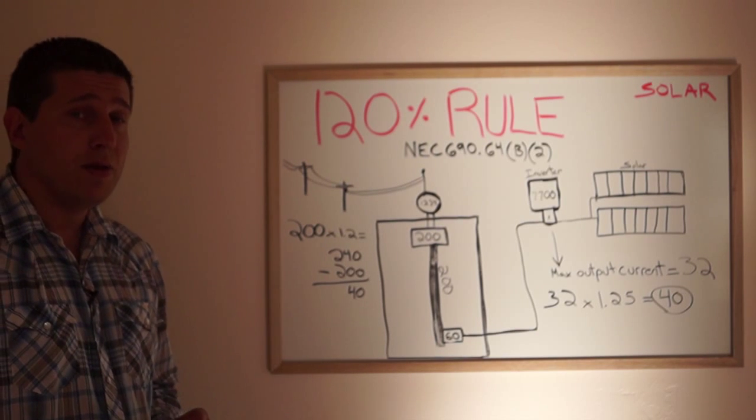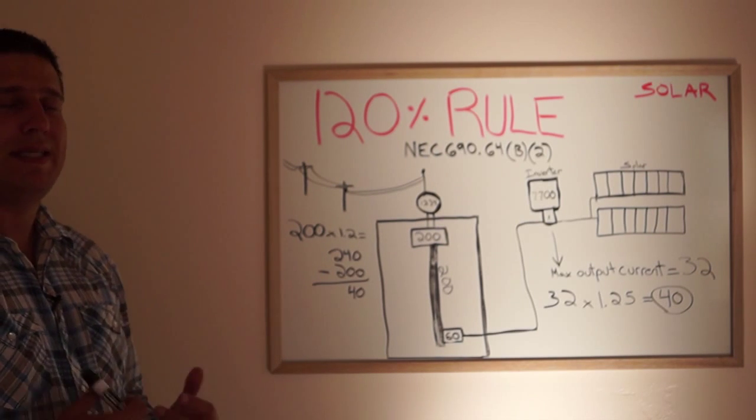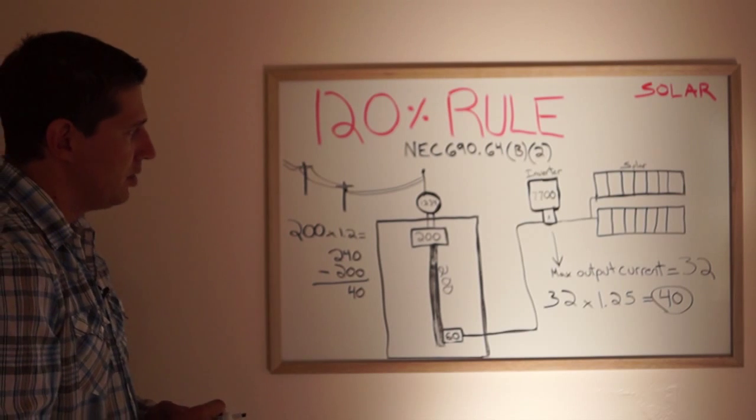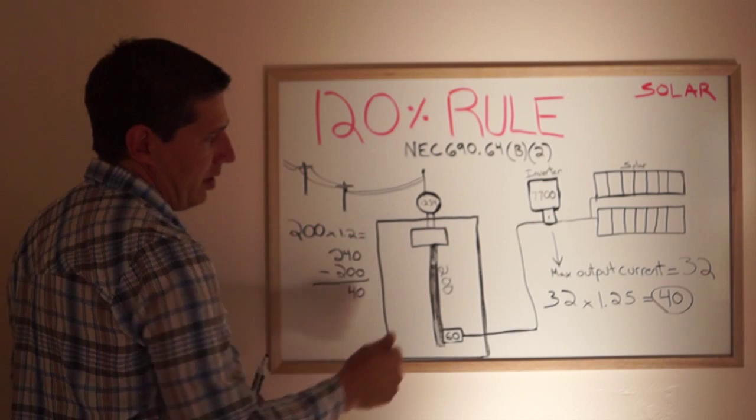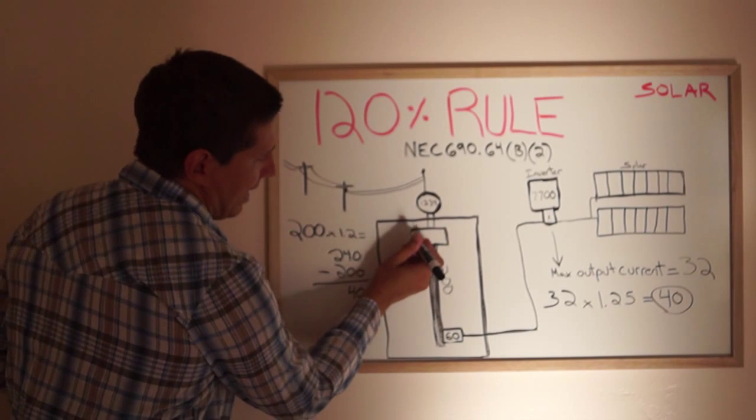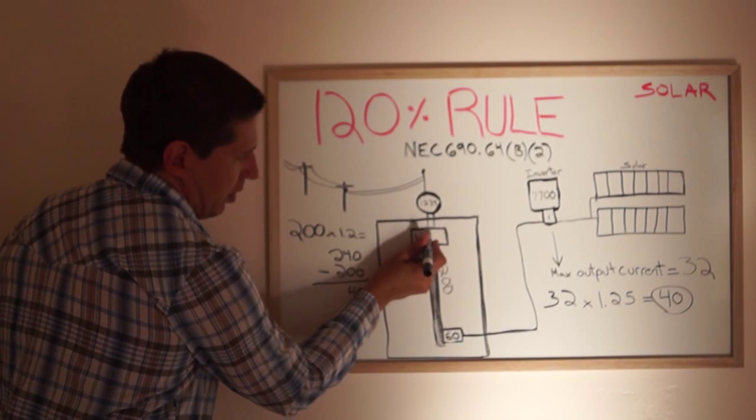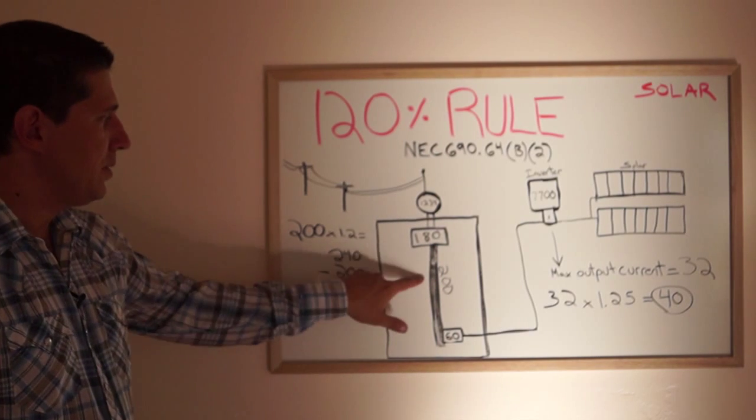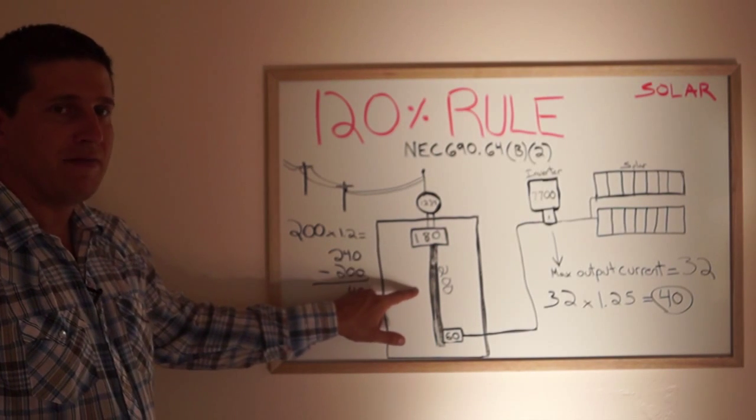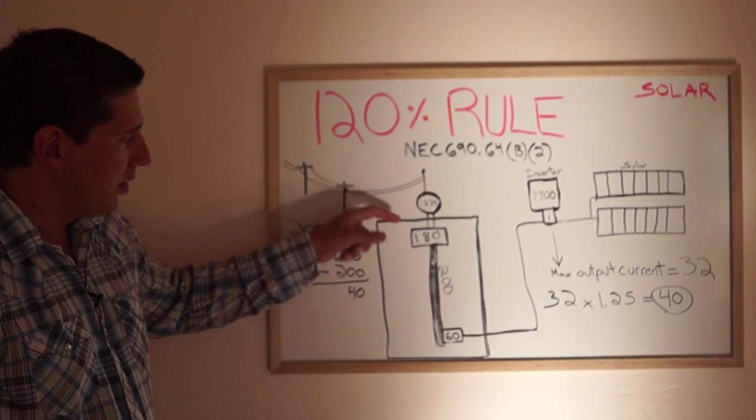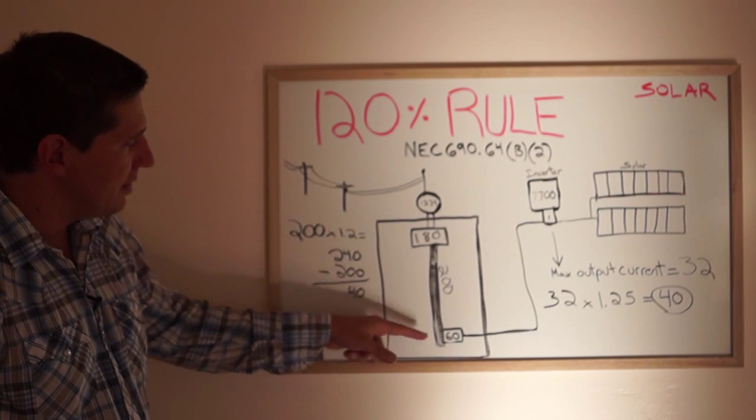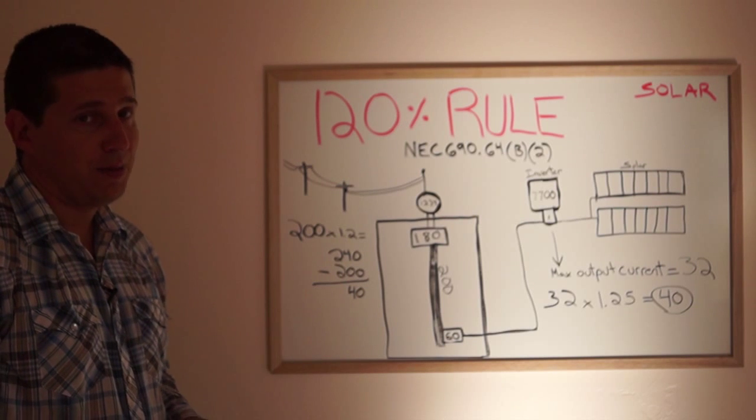So what we can do is we can actually do what's called a derate of the main panel, of the main breaker. So we take that 200 amp out. We look for a 180 amp breaker. And now that bus bar can never have more than 240 amps at one time. 180 amps from the main and 60 amps from the solar equals 240.